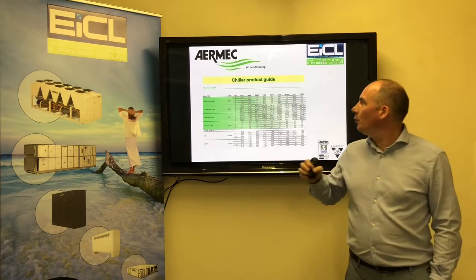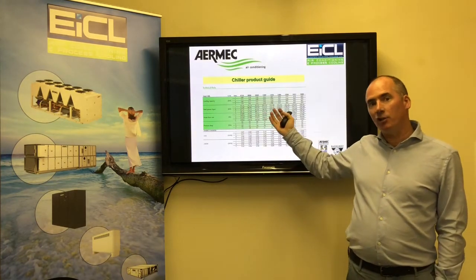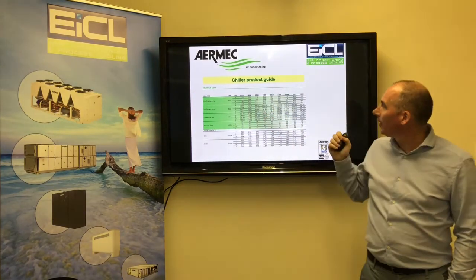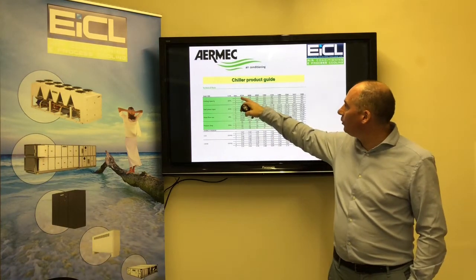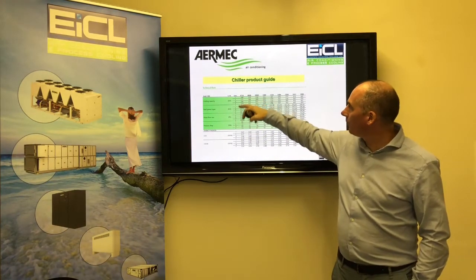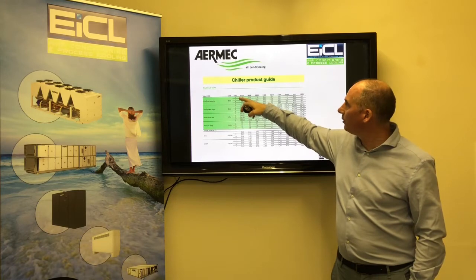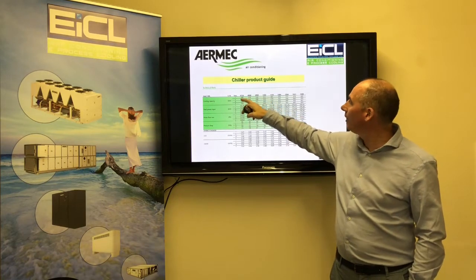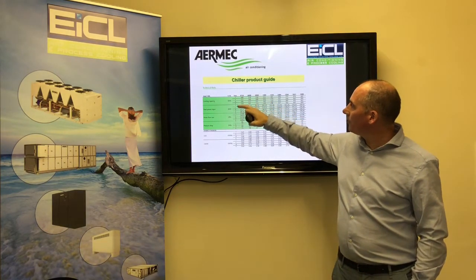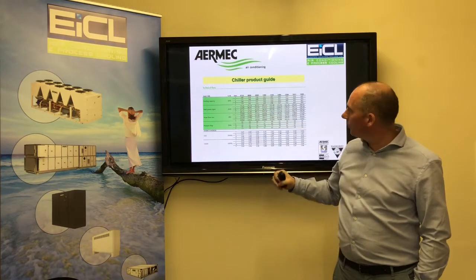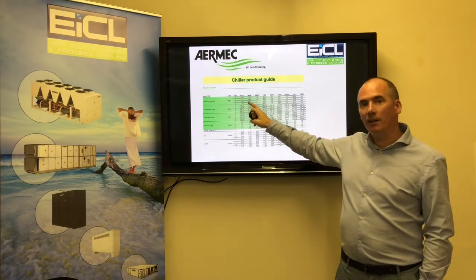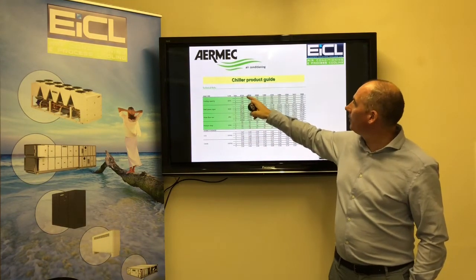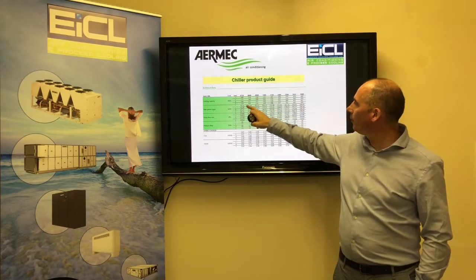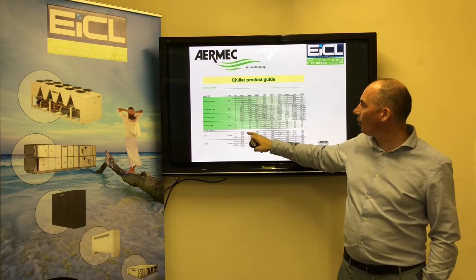Just to make the point, if you look at a catalogue, pretty much any chiller manufacturer's catalogue or product guide, you will see they'll give you the cooling capacity for whatever model. So for example here, this is an AERMEC NRL range. They would have a standard, low noise, high efficiency or high efficiency low noise. We have the corresponding input power. So for example, if you divide your cooling capacity by your input power, you will have an EER, your energy efficiency ratio.